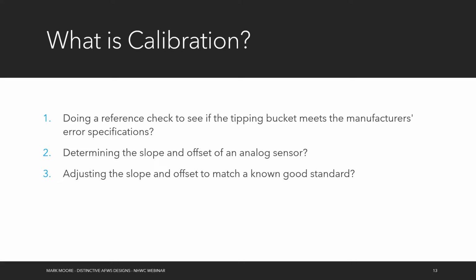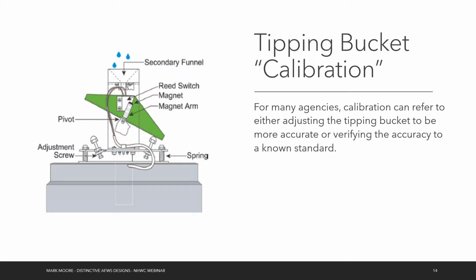But you will often see agencies refer to things like accuracy tests as calibration. And we'll see that a lot with tipping buckets. What is calibration of a tipping bucket? Well, realistically, calibration of a tipping bucket is changing these adjustment screws you can see in this diagram, up or down, to adjust the rate at which that bucket tips. Anything else is really more of an accuracy test than a calibration. And that's not to say accuracy tests aren't important, but I just want to make sure we're using good terminology when we're talking about calibrations versus accuracy tests.